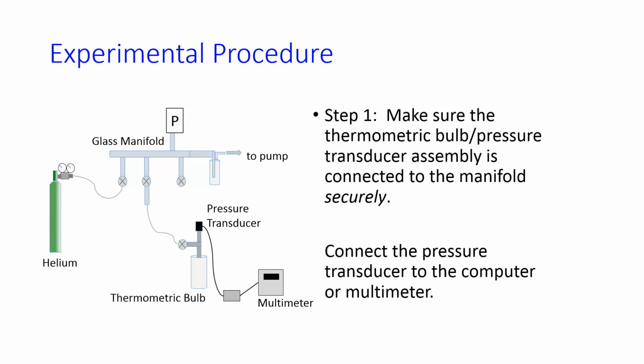So the procedure. First thing you're going to need to do is to make sure all the connections are made securely. So in addition to the ones on the helium cylinder, you're also going to need to make sure that your thermometric bulb is connected to the valves that are on top of it and also connected to the manifold securely.